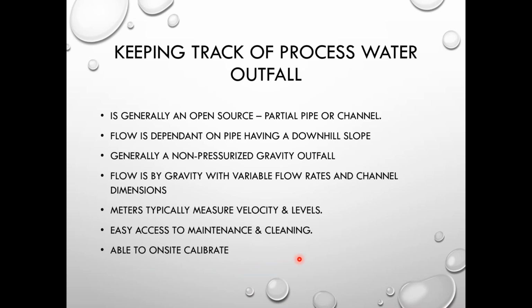The last part of it, being able to calibrate on site, is much easier for open channel flow meters. When you've got a full pipe flow meter, there really is no way of doing a wet calibration because you have no way of getting to those flows other than doing a test on the system. These, and I'll go through them, are transit time ultrasonic flow meters that you can put on a pipe, and those are at about 2% accuracies. But those are just testing it with a second meter.